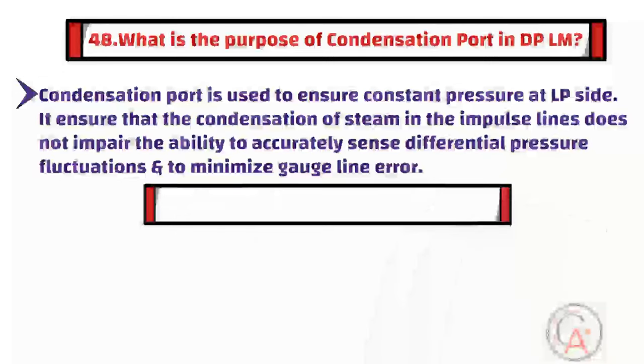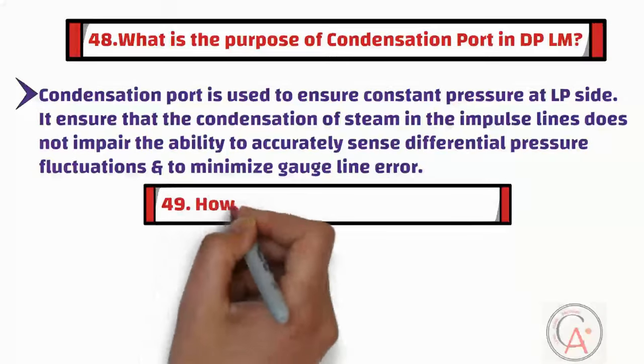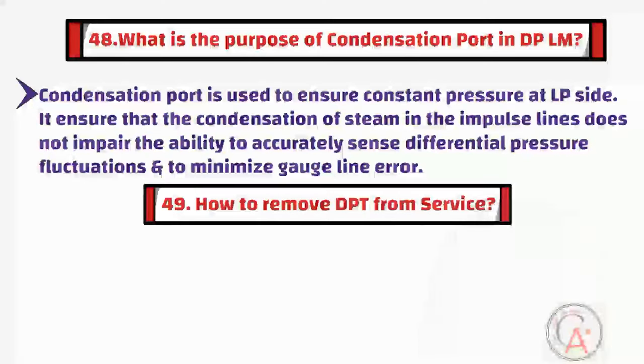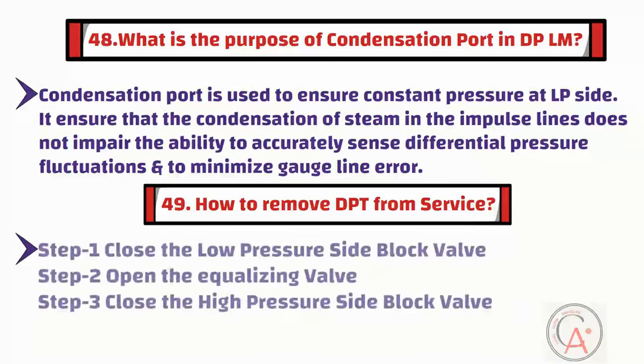The forty-ninth question is: how to remove a DPT from service? To remove a DPT from service, first close the low-pressure side block valve. Secondly, open the equalizing valve. Finally, close the high-pressure side block valve.